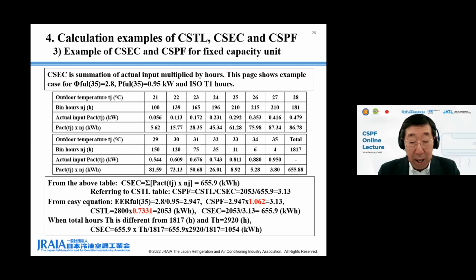CSEC is the sum of actual input multiplied by hours for all operating temperatures. This page shows a calculation example of a fixed capacity unit for 35 degrees C, full capacity 2.8 and full input 0.95 kilowatt, and ISO T1 bin hours. In this table, the first line shows outdoor temperature TJ. The second line shows ISO T1 bin hours NJ at each TJ.